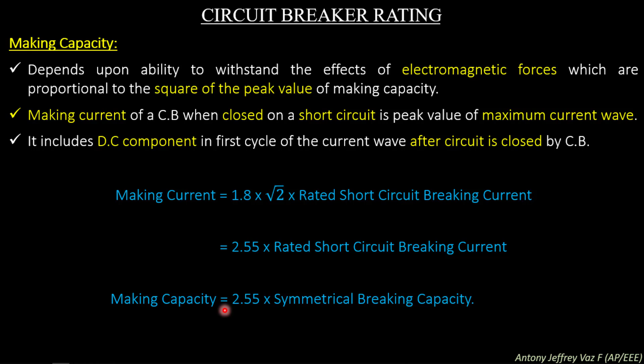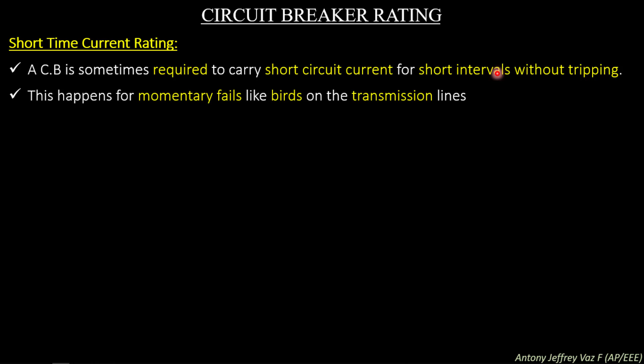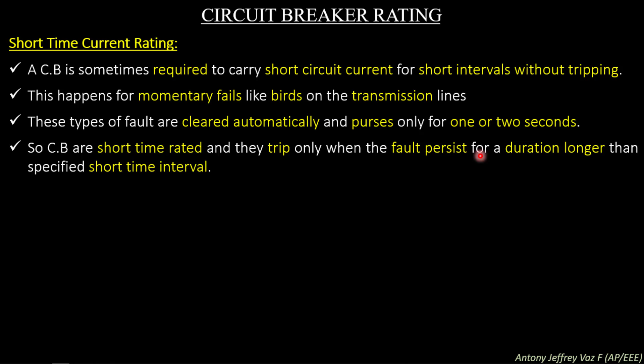The last one is short time current rating. We have explained earlier, a circuit breaker is sometimes required to carry short circuit current for a short interval of time without tripping. This happens for momentary faults like birds on the transmission line. These types of faults are cleared automatically and persist for only 1 or 2 seconds. So circuit breakers are short time rated and they trip only when the fault persists for a duration longer than the specified short time interval.